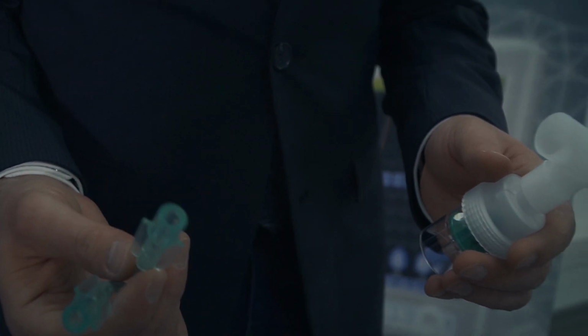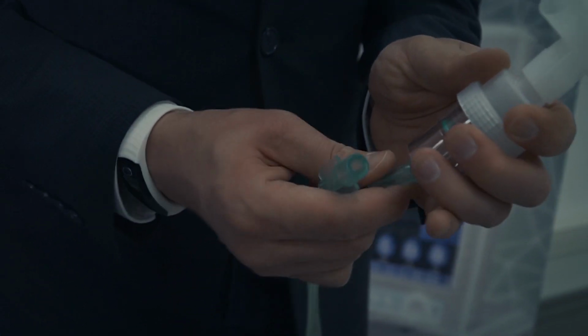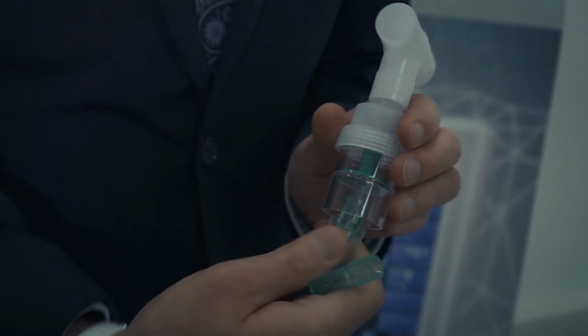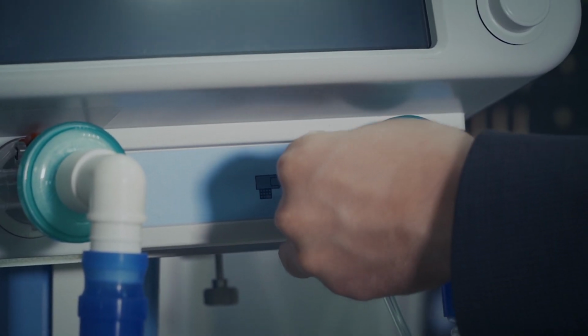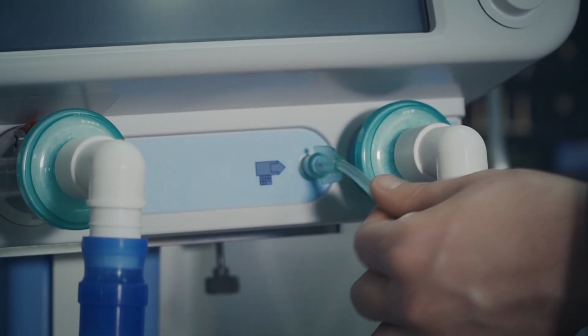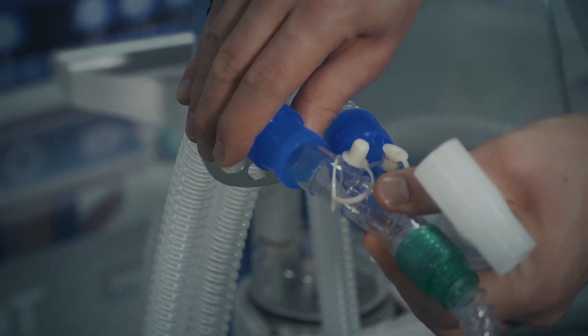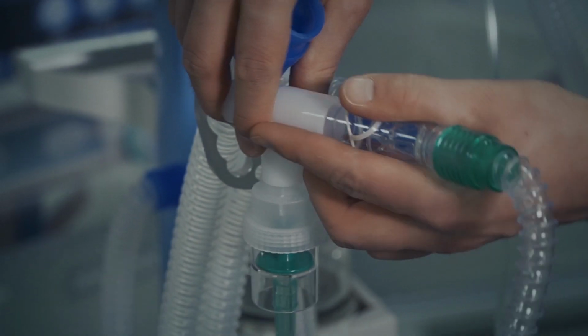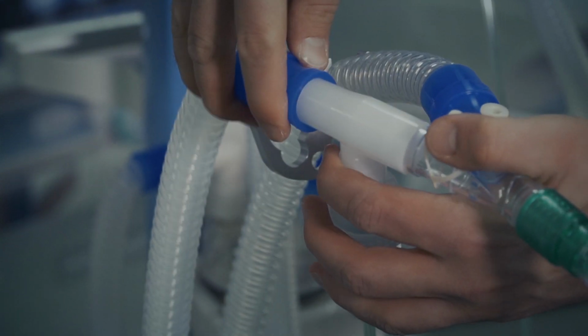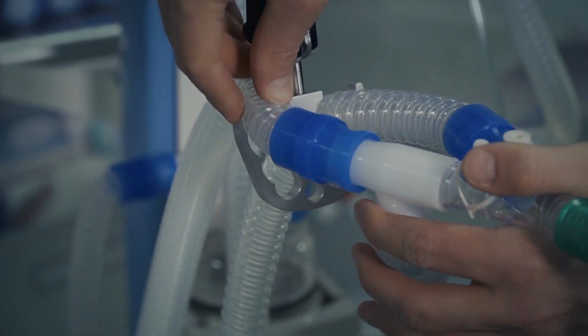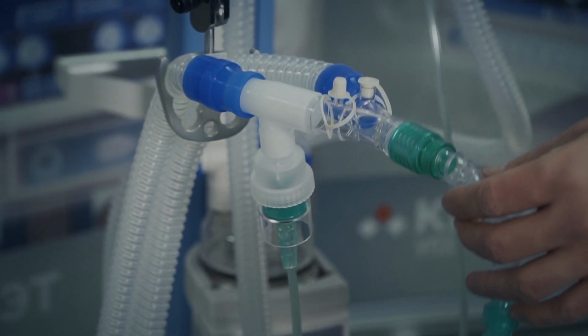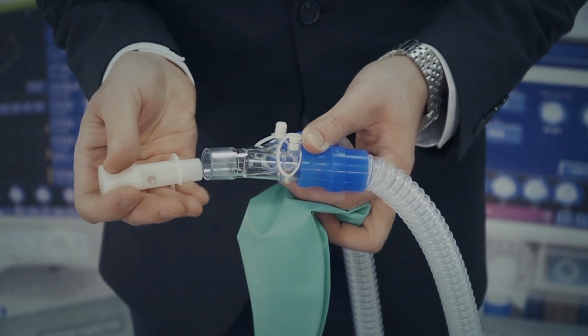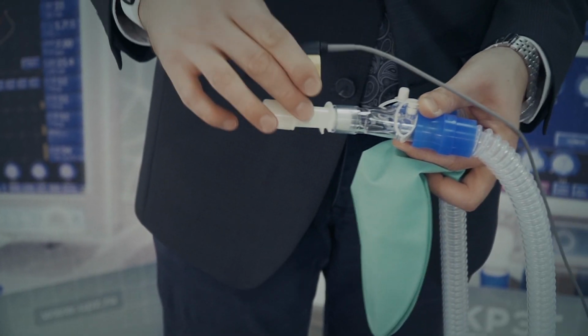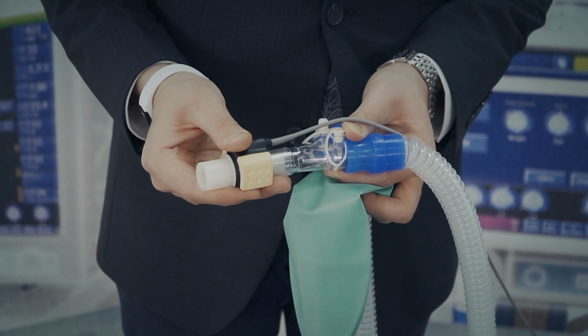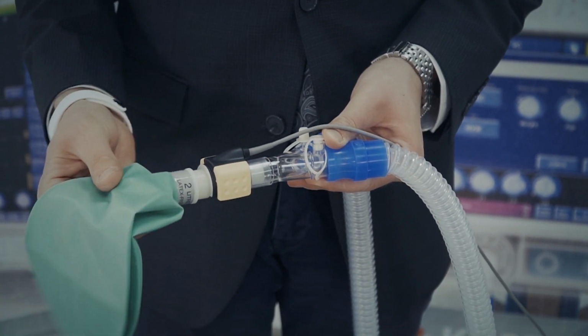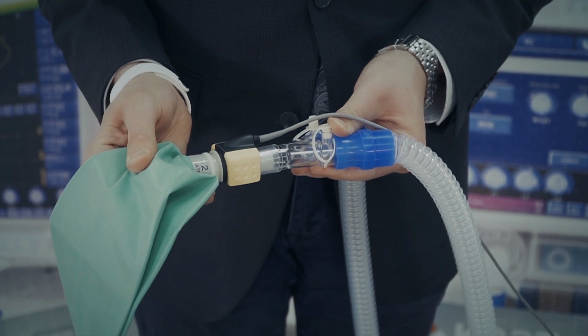If nebulizer is used, connect oxygen tube to pneumatic nebulizer connector on the ventilator body. Incorporate the nebulizer in the breathing circuit on the inspiration line upstream of patient's Y. If capnography sensor is used, incorporate special adapter in the circuit between patient's Y and endotracheal tube. Install capnography sensor on the adapter and press slightly until it engages.